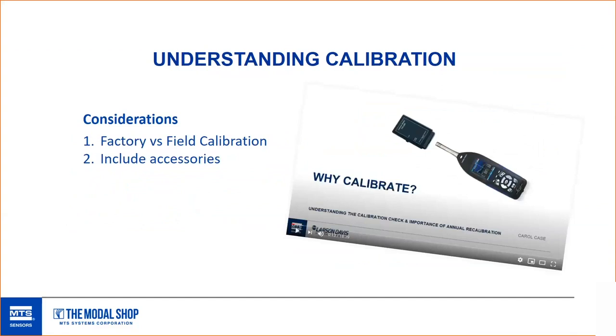The factory calibration often tests all parameters, from the lowest level of the noise floor to the highest level where it becomes nonlinear, then the lowest frequency beyond what's measured to the highest frequency, to make sure it exceeds every part of the A-weight filter shape, for example, and every part of a third octave filter shape for each one is tested. The microphone is also tested the same way across the full frequency spectrum.